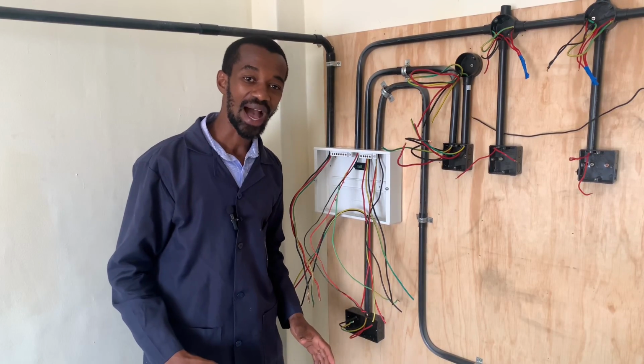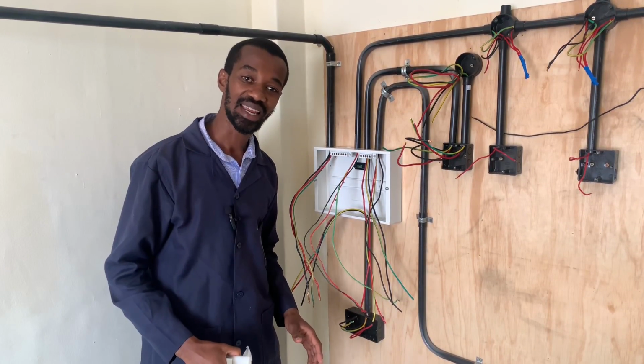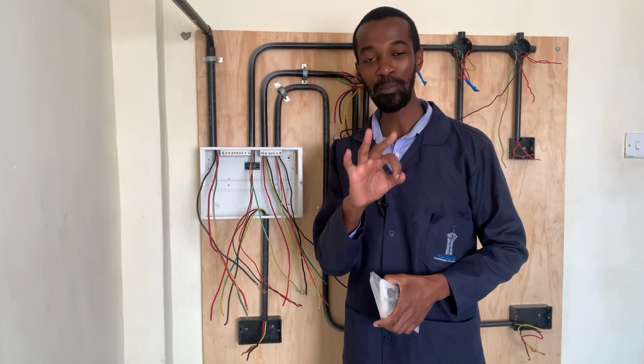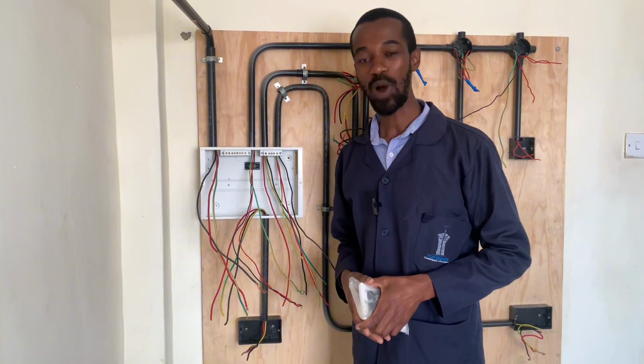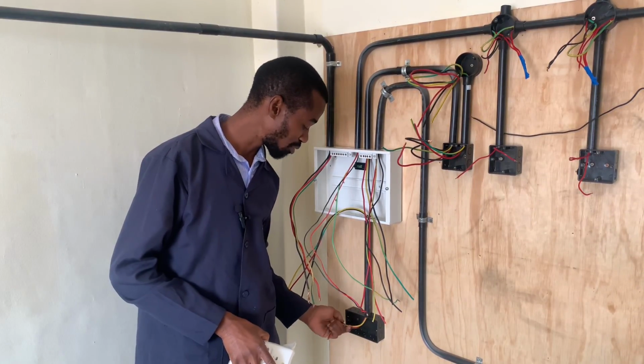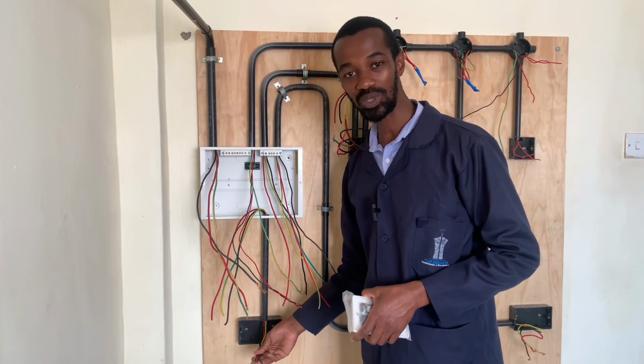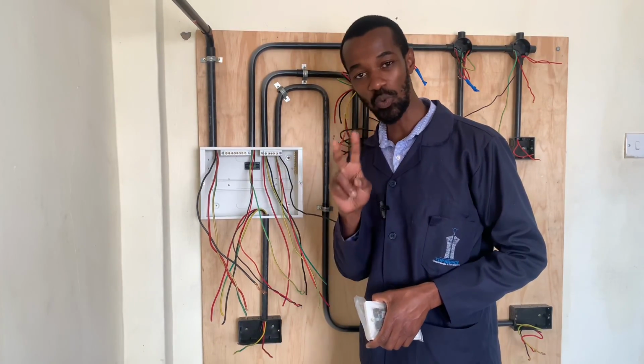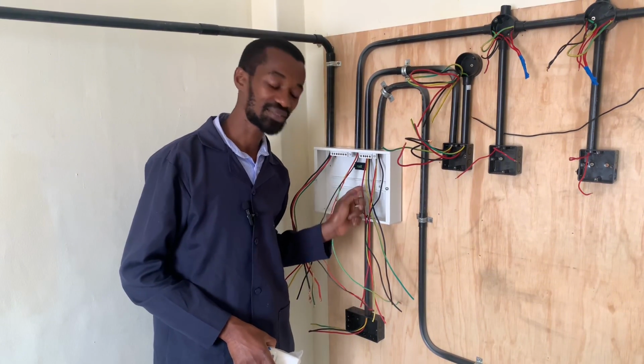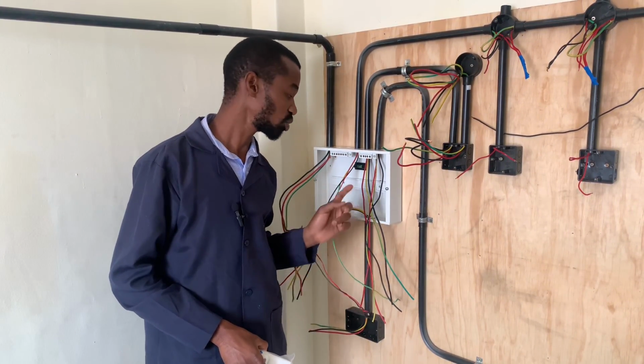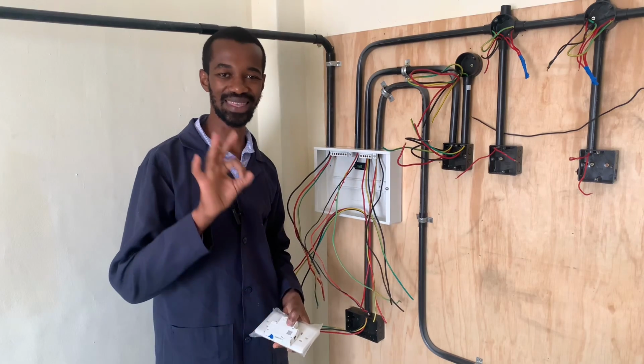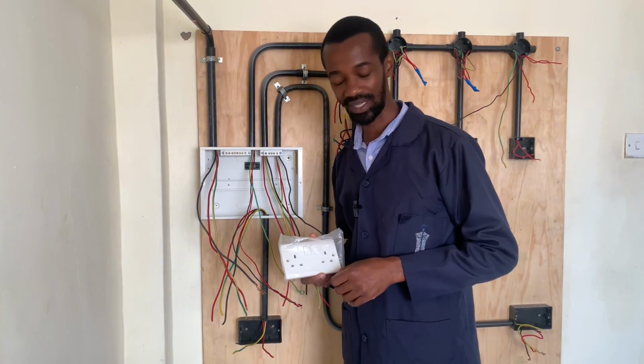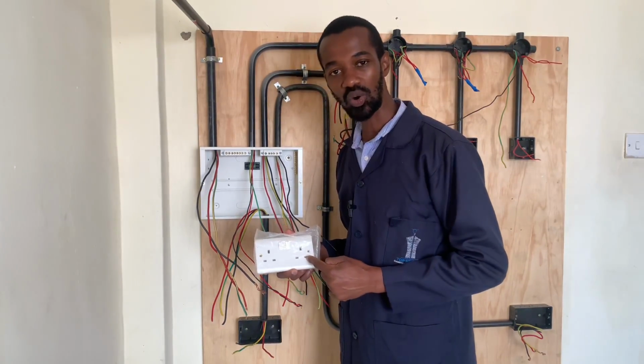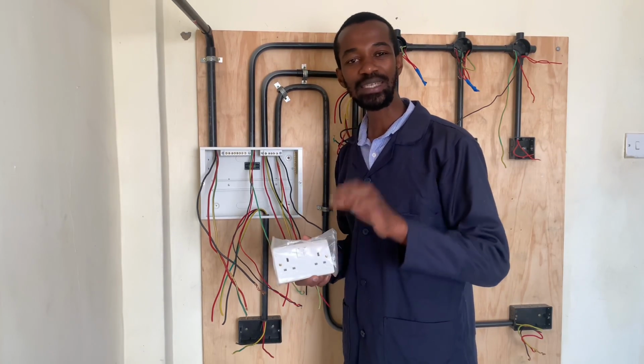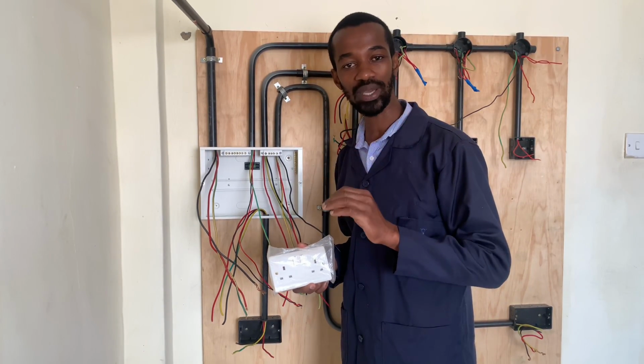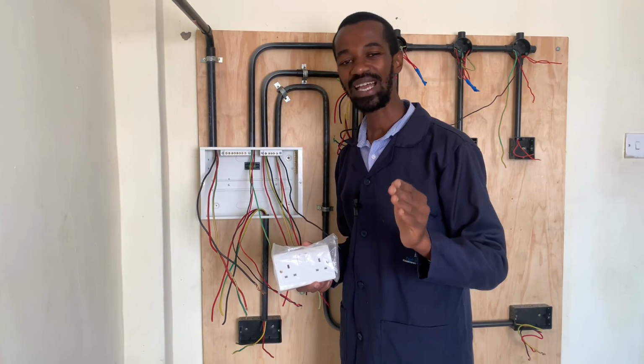If I were to wire a socket outlet in the kitchen, I would consider three important facts: the size of the cable supplying that socket with current, the circuit breaker that serves that socket in the consumer unit, and the type of socket, which must be a twin socket and a quality one that can handle large currents.